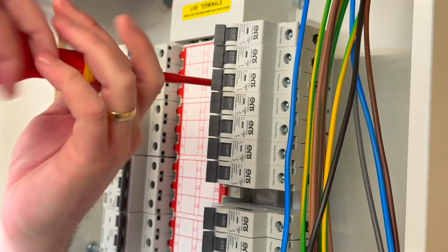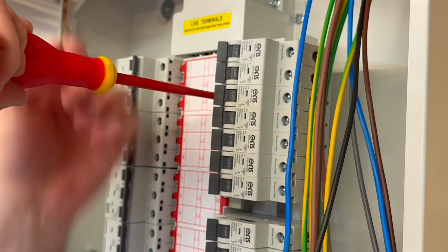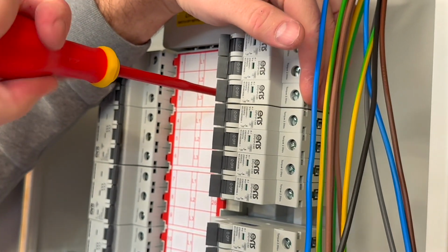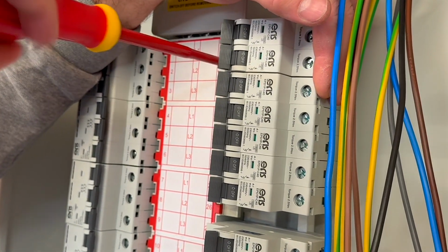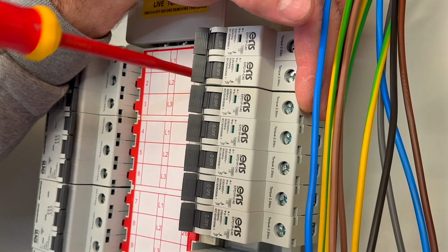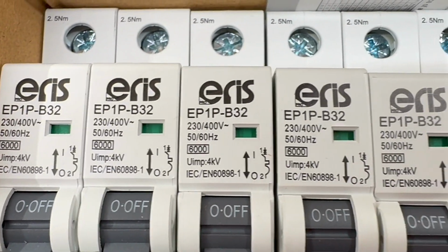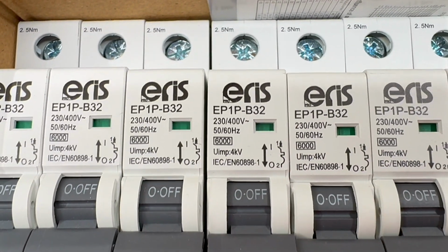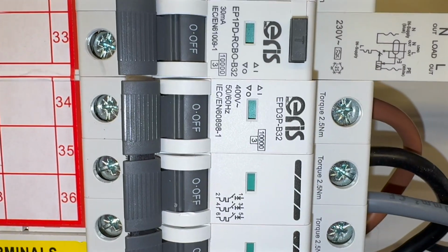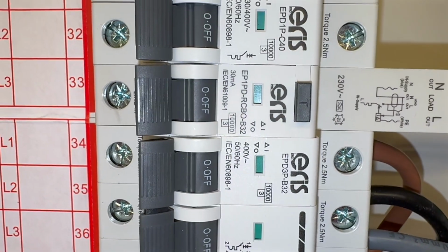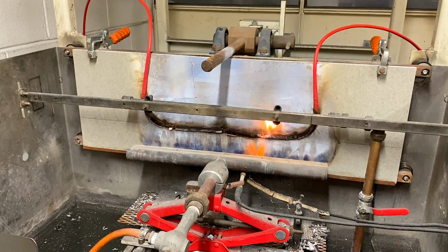Let's take a closer look at circuit protection devices. At first glance, single-pole devices might seem similar to those used in residential consumer units, but a key distinction lies in their fault current ratings. Residential devices typically have a 6 kiloamp fault current rating, while industrial applications where fault currents can be significantly higher require devices rated at 10 kiloamps. They are also tested to work in more arduous environments in industrial applications such as factories.